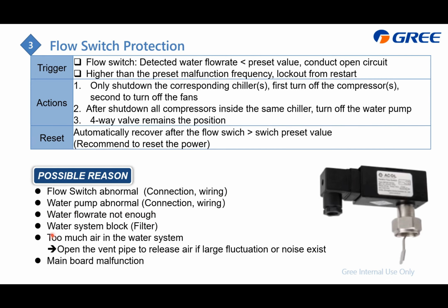And maybe the water system has a blockage, like the filter, or the soft connection is not that good, or maybe there's too much air inside the water system. At that time, you can check the water pressure gauge. If the pointer vibrates a lot, that indicates too much air inside. Or maybe there's something wrong with the main board.